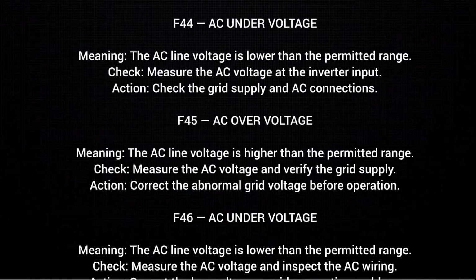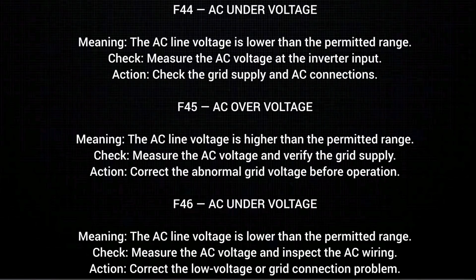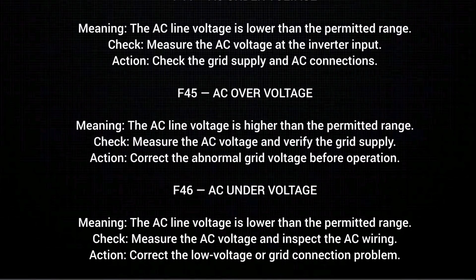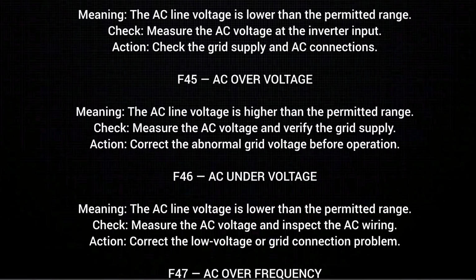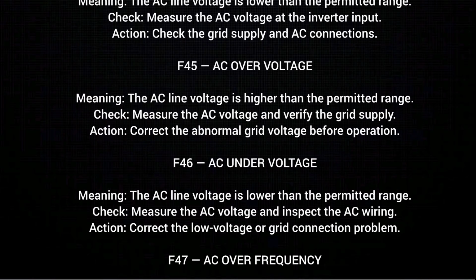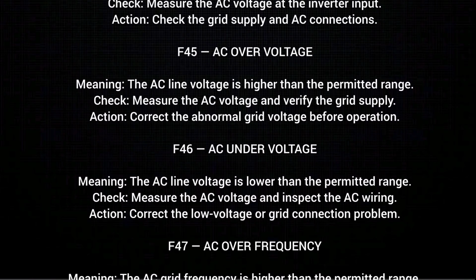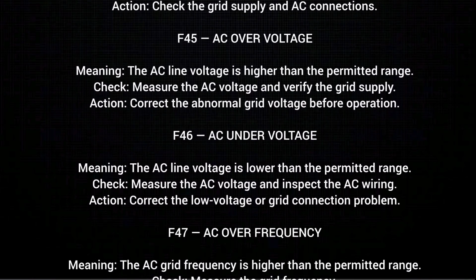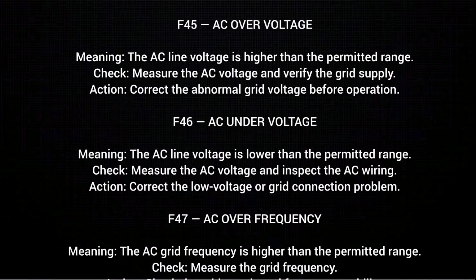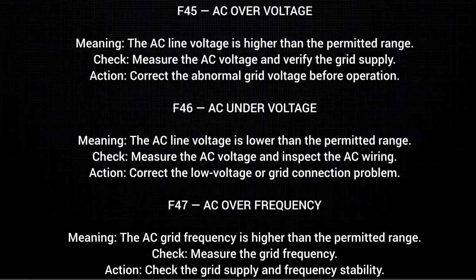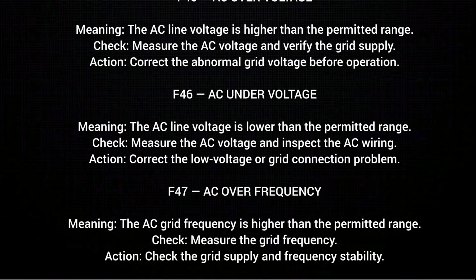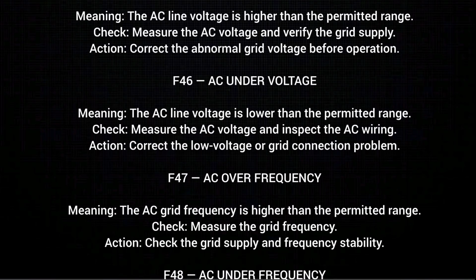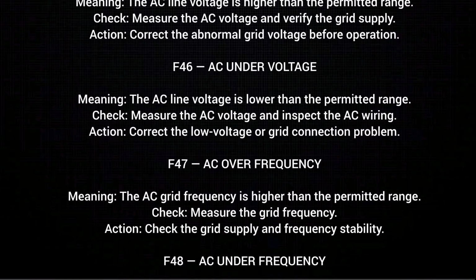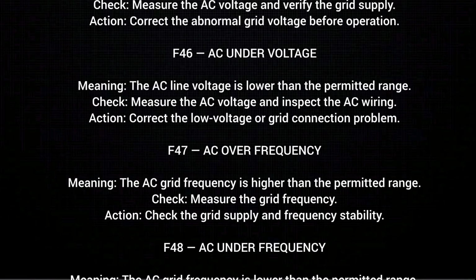F46. AC under voltage, meaning the AC line voltage is lower than the permitted range. Check. Measure the AC voltage and inspect the AC wiring. Action. Correct the low voltage or grid connection problem. F47. AC over frequency, meaning the AC grid frequency is higher than the permitted range. Check. Measure the grid frequency. Action. Check the grid supply and frequency stability.